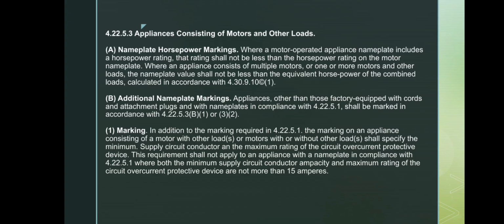Next, under additional nameplate markings, appliances that do not come factory equipped with a cord and plug must follow additional marking rules aside from the basic nameplate information. The appliances must also indicate the minimum supply circuit conductor ampacity, meaning the minimum wire size needed, and the maximum rating of the overcurrent protective device, like a fuse or circuit breaker. This extra marking is not required if the appliance already complies with the basic nameplate rules and both values do not exceed 15 amperes.